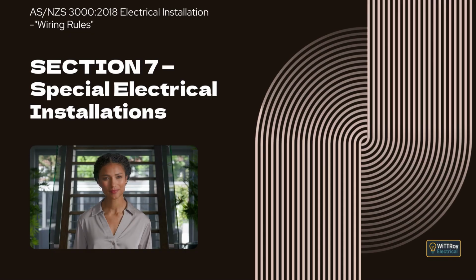The clause explains that every outgoing circuit must be individually protected and include additional earth leakage protection where required. It also explains when a circuit may be considered protected against prospective short-circuit earth fault currents due to the limited output capability of the generation system. Clause 7.3.5.2.2 RCDs. This clause explains that the waveform of fault current to earth from electricity generation systems can affect the operation of RCDs and must be considered when selecting the RCD type. Where an inverter is used, the RCD must be suitable for the earth fault waveform produced by that inverter and must be installed in accordance with the manufacturer's instructions.